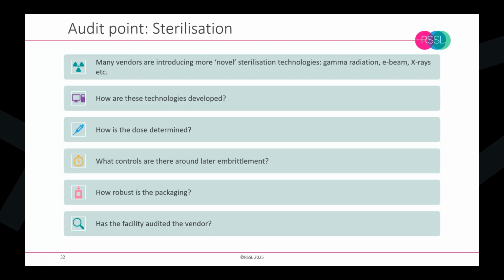Was this based on product composition? Was it based on mass? Was it based on the dimensions of objects? And what's the logic behind that? Many autoclave validations will work on total mass, but it's been shown through studies that something like a very narrow piece of silicone tubing, which would not weigh very much at all, but targeting heat in the center of that, can be severely problematic.